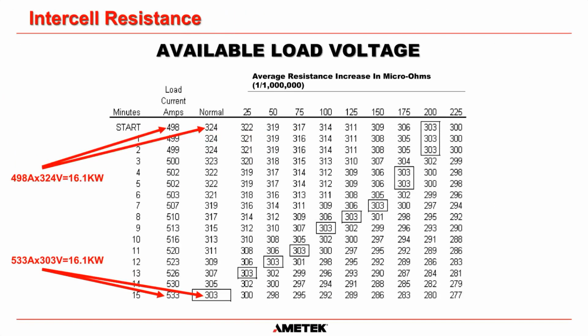And here's why. This is kind of a complicated table, so hopefully I can explain what's going on. This is a capacity test being performed on a battery, and they're taking out about 500 amps. When you do a test on a battery, it is a constant power test. This second column is volts, the voltage of the battery as the capacity test goes through its 15-minute period. At the very start, 498 amps times 324 volts means we are taking 16.1 kilowatts out of the battery.